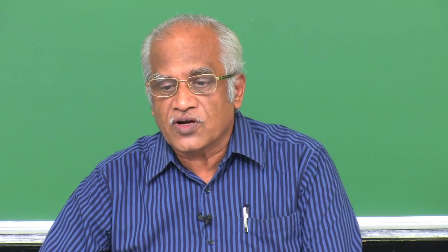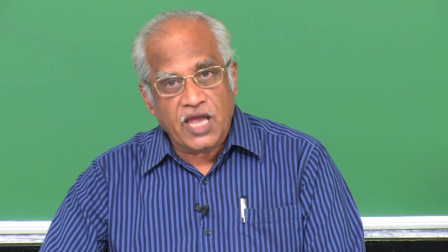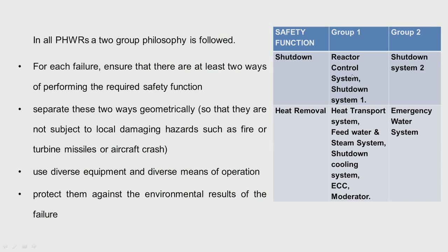Looking at the safety function of shutdown: the reactor control system — control rods and adjuster rods — along with shutdown system one are grouped into group one. Shutdown system two is the other group, so there is independence between group one and group two. For heat removal, the heat transport system, feed water, steam system, shutdown cooling systems, emergency core cooling, and moderator are all in one group. The emergency water system is the other independent group. This two-group philosophy is what is followed in our pressurized heavy water reactors.